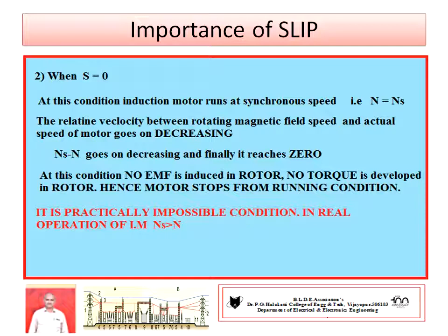The second condition: when slip s equals 0. At this condition the induction motor would run at synchronous speed, that is N equals Ns. The relative velocity between the rotating magnetic field speed and the actual rotor speed — that is Ns minus N — goes on decreasing until it finally reaches zero. When it reaches zero, the speed of the motor equals synchronous speed N equals Ns. At this condition, no EMF is induced in the rotor circuit, hence no torque is developed, and the motor stops from the running condition.